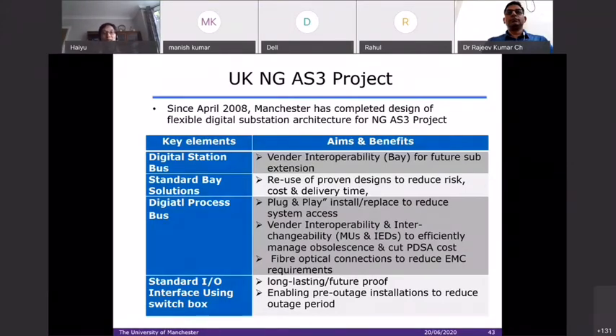So let me give you an example, a different perspective. We look at the communication, but we don't really care what the communication is - we just choose it and look at the architecture. Vendor interoperability for the bay, for future substation extension - that's one of our requirements. The standard bay reuse proves the design and reduces risk and delivery time.